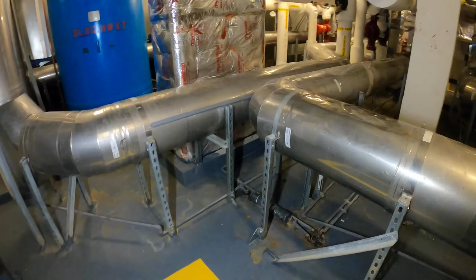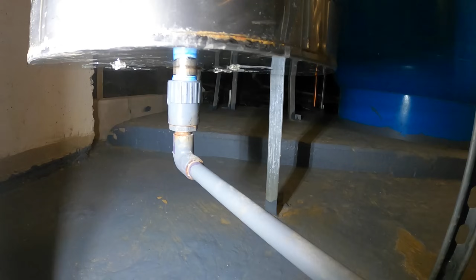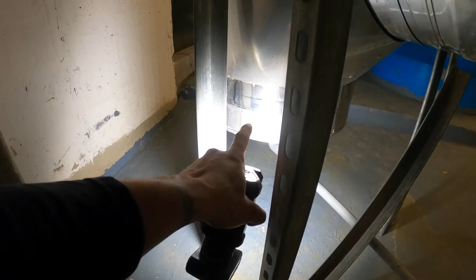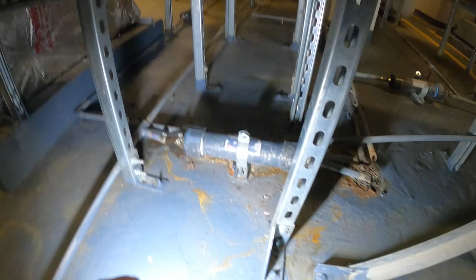I had a service call here the other week where this duct, which is the exhaust for that boiler, each boiler has its own exhaust as you can see. This exhaust has a condensate pipe connected to it, and this thing was leaking water like crazy. When I pulled out this condensate neutralizer kit, water just flowed out, and I might have a video on my phone. Once I pulled out this fitting, water just poured right out. So these things were pretty much clogged up.